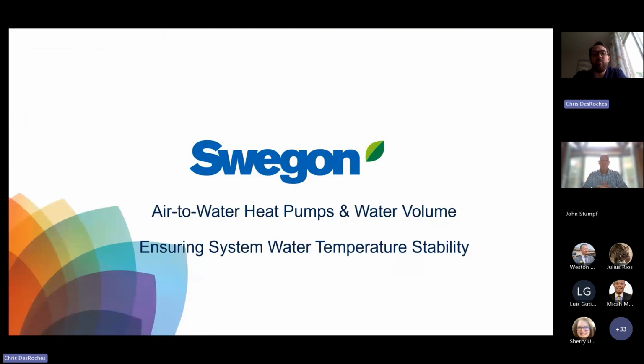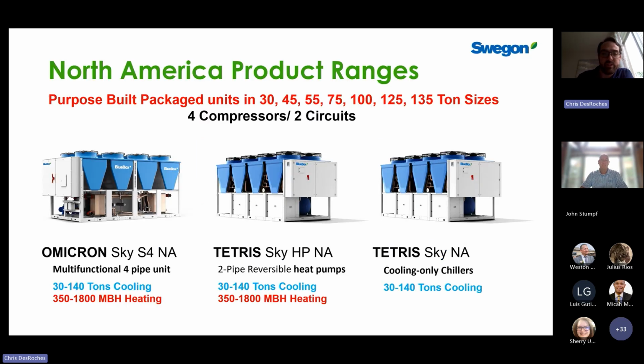We're going to talk today about water volume specific to air-to-water heat pumps and how to think about defrost to make sure that we have good water temperature stability. I was here a couple months ago doing a talk, so just a quick recap for anyone who missed the last session on Swegon. We have air-to-water heat pumps that we launched last year, two-pipe reversible heat pumps, and four-pipe multifunction units with heat recovery to do heating and cooling simultaneously, with heat recovery always happening, even when you have unbalanced loads. These are monoblock package units with 4 compressors per machine, with 2 independent refrigerant circuits. And one of the key points that we're going to talk about today is the fact that we're able to defrost those 2 circuits independently.